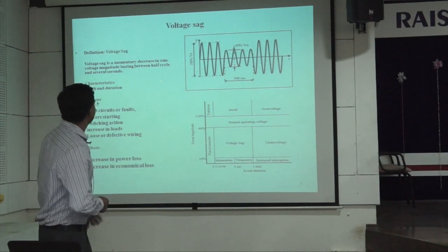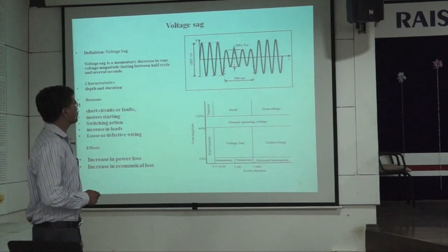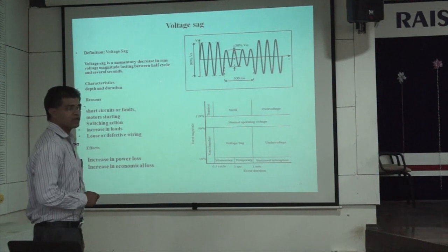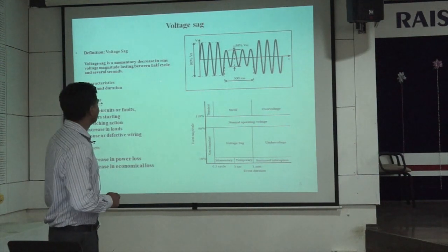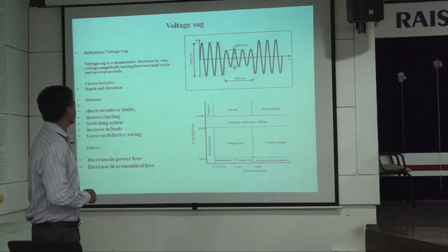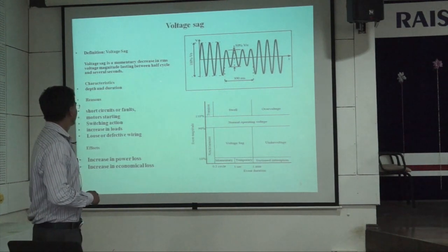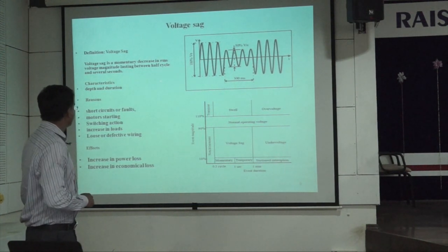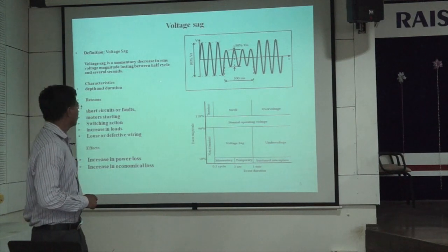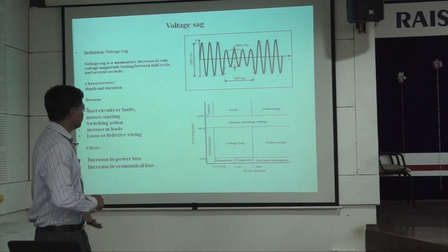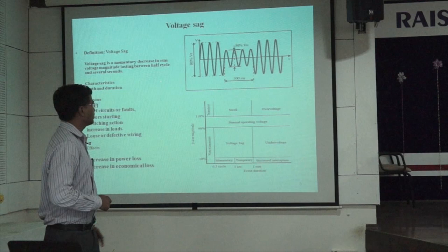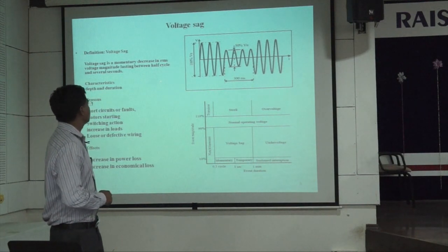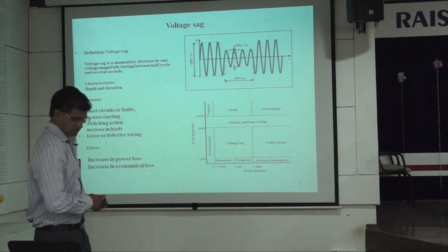So what is voltage sag? Voltage sag is a momentary decrease in RMS voltage lasting between half a cycle to several seconds. It is due to various faults like short circuit fault, motor starting, switching action, increase in the load, loose or defective wiring. There may be various economic losses and power loss in the industries and the domestic appliances.